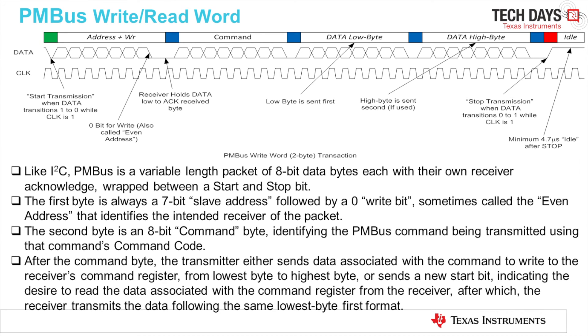This is a typical PMBus write and read word. Like I2C, PMBus is a variable-length packet of 8-bit data bytes, each with their own receiver acknowledge, wrapped between a start and a stop bit. The first byte is always a 7-bit slave address followed by a zero write bit — sometimes called the even address — that identifies the intended receiver of the packet. The second byte is an 8-bit command byte identifying the PMBus command being transmitted using the command's command code. After the command byte, the transmitter either sends data associated with the command to write to the receiver's command register from lowest byte to highest byte, or sends a new start bit indicating the desire to read the data from the receiver, after which the receiver transmits the data following the same lowest-byte-first format.